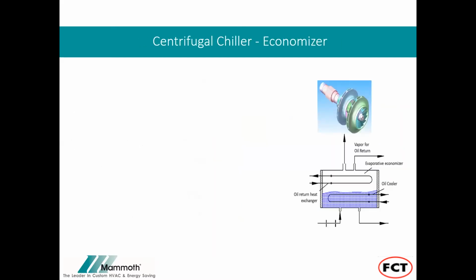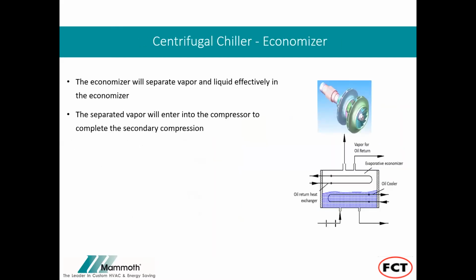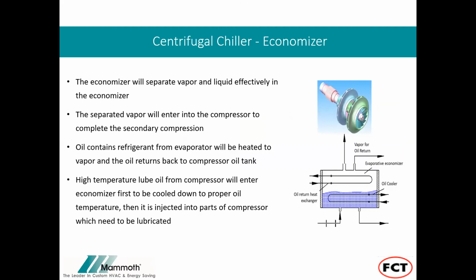In terms of our technology, we also use an economizer to separate the vapor and liquid effectively, and to enable it to enter the compressor for secondary compression. And also the oil containing refrigerant with the evaporator will be heated to vapor, and oil returns back to the compressor oil tank. The high temperature lube oil from the compressor will enter the economizer to be cooled down to proper oil temperature. This is injected into the parts of the compressor which need to be lubricated.